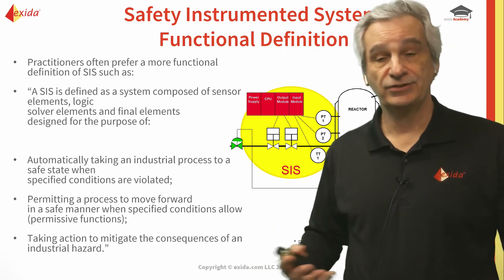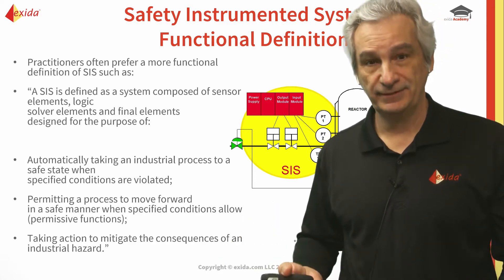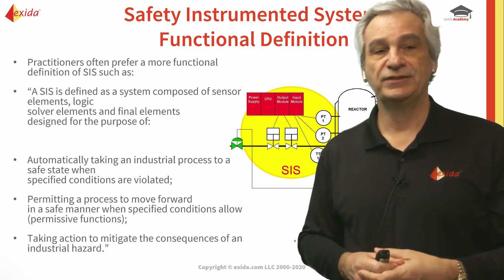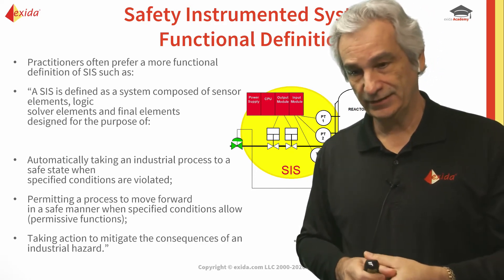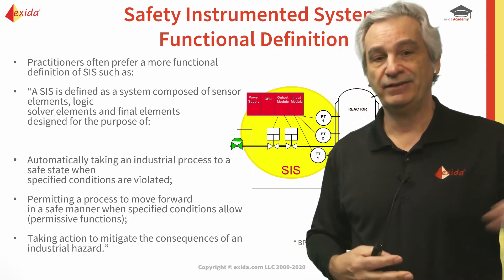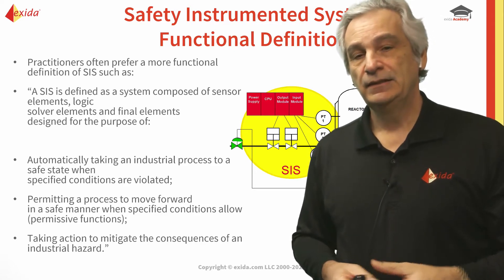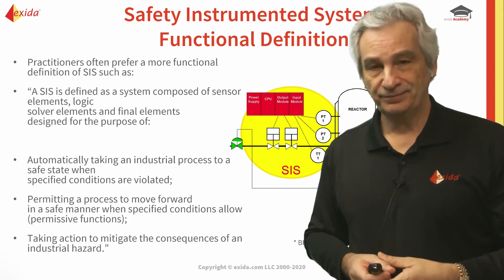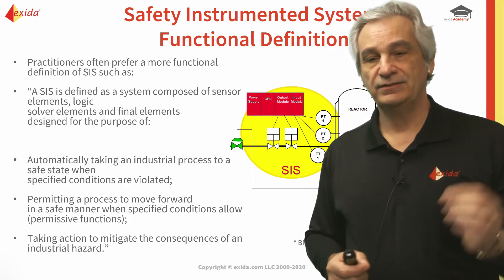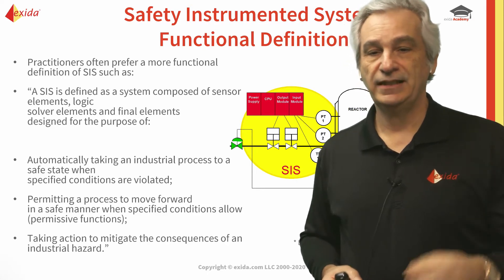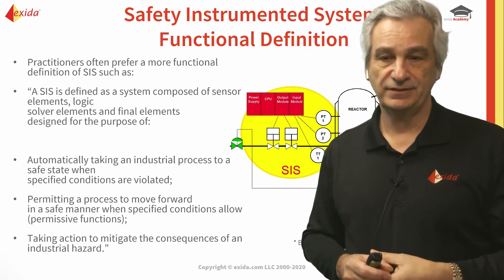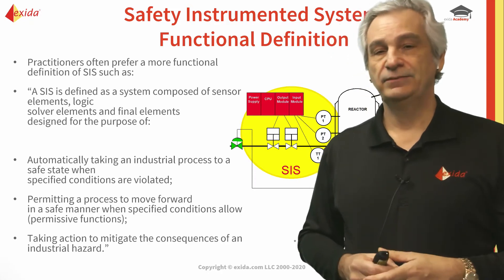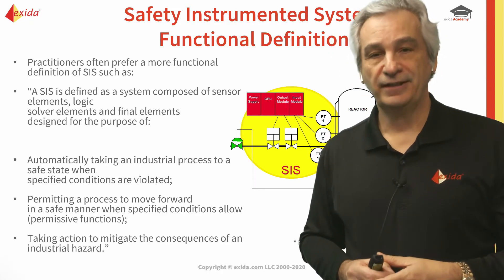A SIS can also permit a process to move forward in a safe manner if the required preconditions — permissives — are present, such as in sequential startup or sequential control. The third function, which is very interesting, is to take action to mitigate the consequences of an industrial hazard, and this one specifically applies to fire and gas.